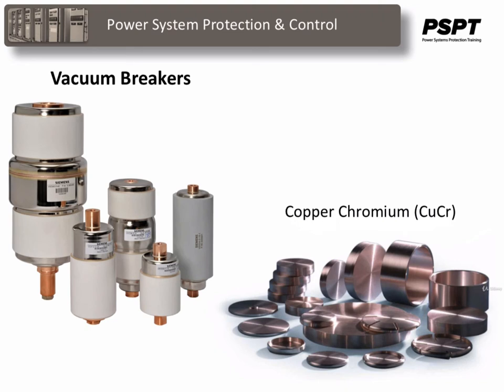The contact geometry is also improving with time. From butt contacts of the early days, it is gradually changing to spiral shape, cup shape, and axial magnetic field contacts. The vacuum circuit breaker today is recognized as the most reliable current interrupting technology for medium voltage switchgear. It requires a minimum of maintenance compared to other circuit breaker technologies.